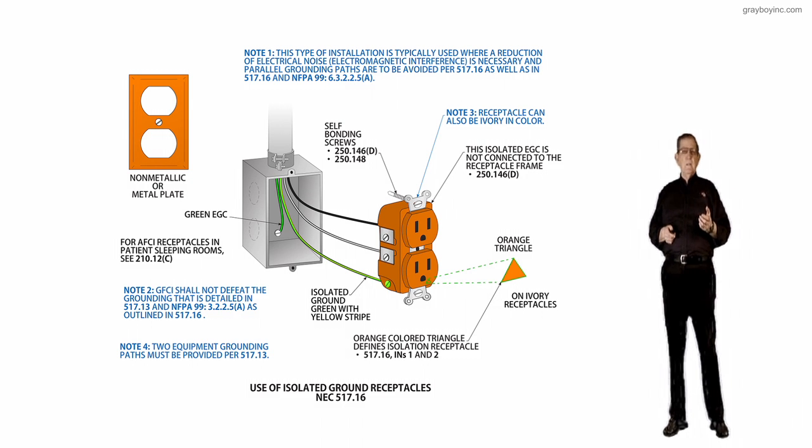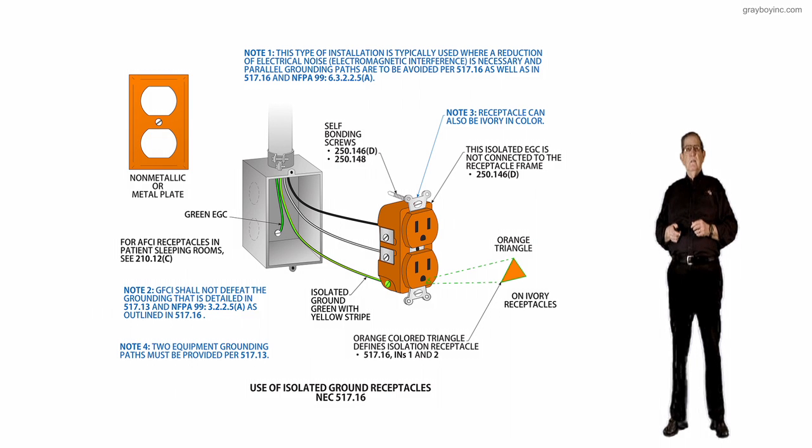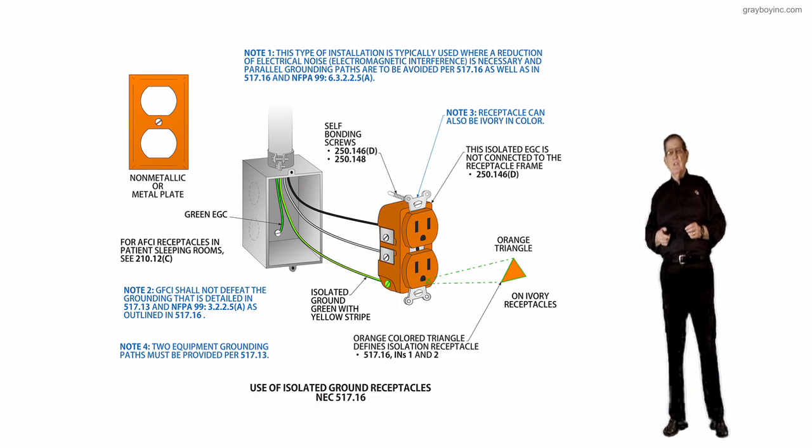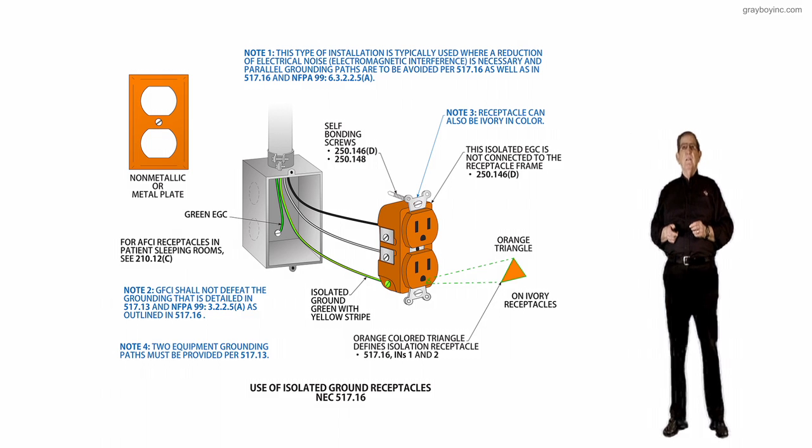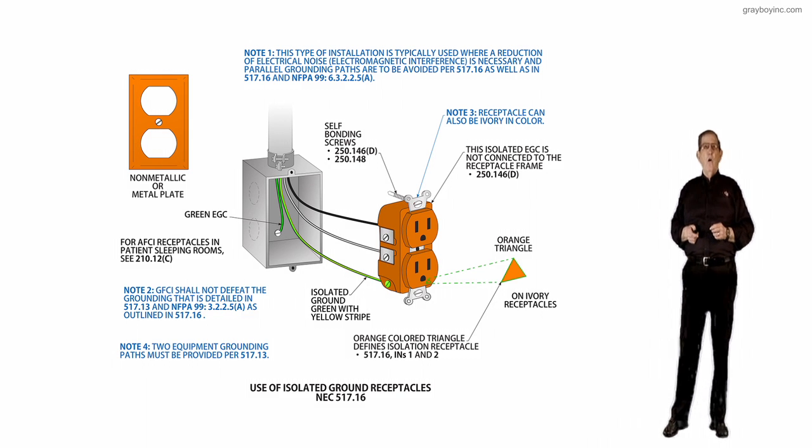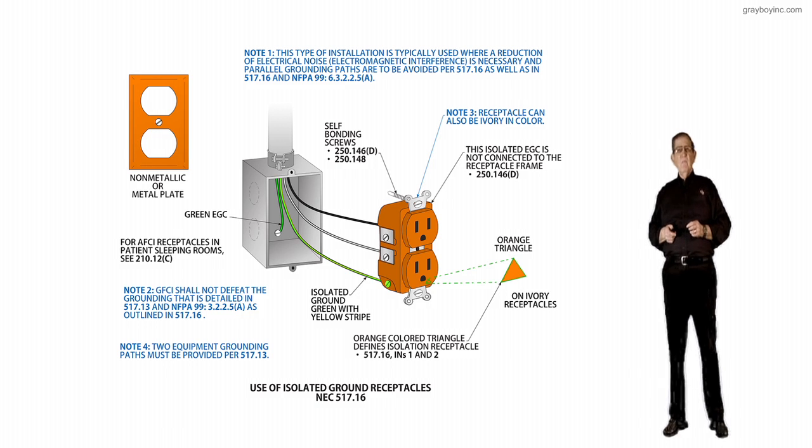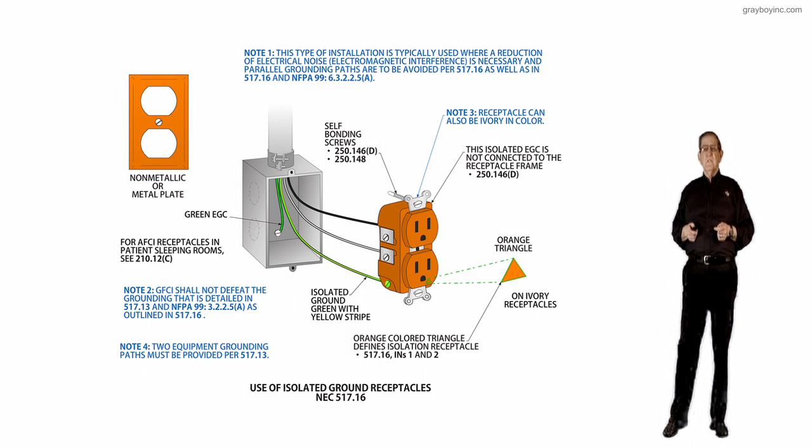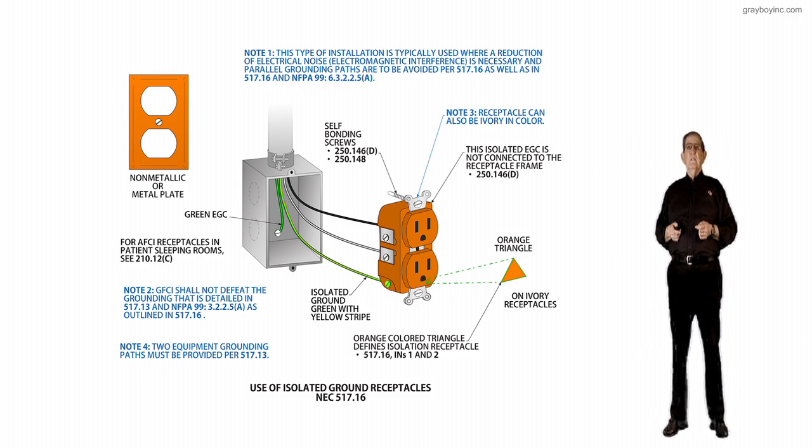Note 3 identifies that the receptacle might be ivory with an orange triangle on it instead of it being completely orange. The final note 4 talks about two equipment grounding paths must be provided by 517.13, which this type of installation using an isolation receptacle will not provide. And then notice sometimes you might even have an orange non-metallic or metal plate according to whatever the administration of the healthcare facility may demand. Instead of it being ivory with your orange triangle, it might be an orange plate. Review this section very carefully and watch out about it.